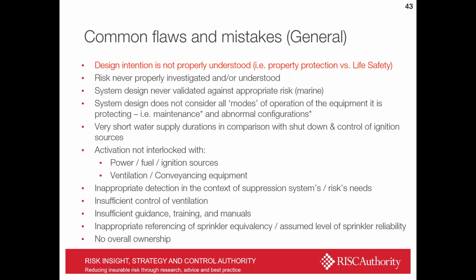appropriate risk. We've been through a period where we see a lot of onshore water mist applications being justified by experiments conducted for the marine environments, which use very different fuels, and obviously the enclosure details are very different also. And you need to question whether that is appropriate or not. Also, a key one is that the system design doesn't necessarily consider all modes of operation of the equipment it's protecting. And we've seen some very large losses where the system probably would have worked fine had the equipment been configured as it's normally configured. But then fires don't generally manifest when things are normal. Fires happen when abnormal stuff happens, and maybe if a fryer hood has been lifted or something, then the system fails to operate because the ventilation details have now changed.